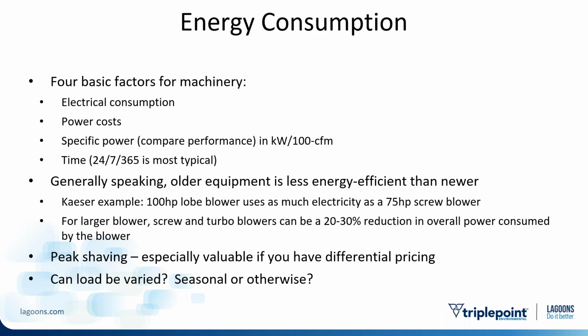These guys were spending $50,000 a month, and we were able to eliminate that bill just by changing how their compressors turned on and off. There probably won't be an example that extreme for a wastewater treatment plant, but if you look at your bill and see demand charges, you want to think about staging equipment on and off to avoid being charged those. You're using the same amount of energy, you're just creating less stress for the utility, and they'll reward you by not assessing those demand charges.